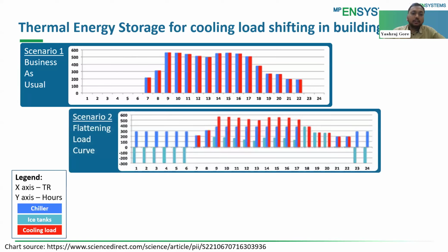But in scenario two, we can see that your chillers will be operational in the non-peak hours, where you store your thermal energy and utilize it across the day, where you provide additional support from the thermal energy storage and reduce your load requirement. And in the peak time, you completely use your thermal energy storage so that you won't have the burden on the grid. So that is how you can flatten the load curve.